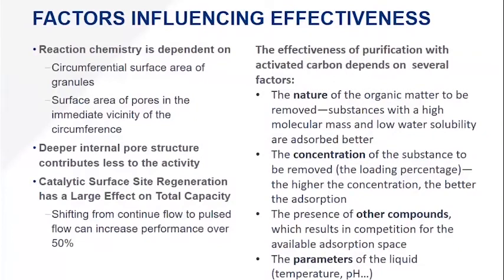The presence of other compounds results in competition for available space. This is one of the reasons why we want filters changed out on time, because there is chemical preference to what is removed by activated carbon. Once you load carbon to a specific point, other contaminants that are more preferential may start to push those contaminants off the activated carbon as it becomes saturated. That's why we have a change-out schedule. Parameters of the liquid itself — temperature, pH, and things like that — will also impact the effectiveness of activated carbon.